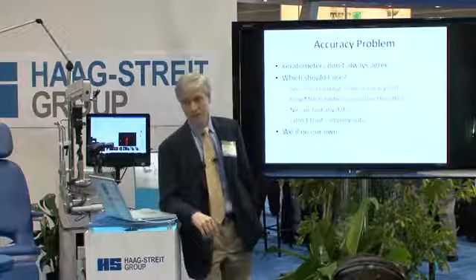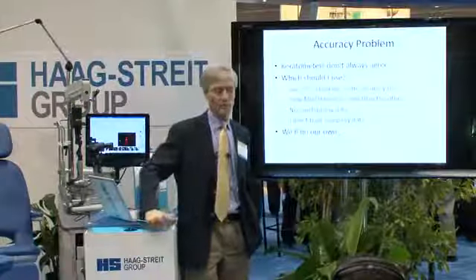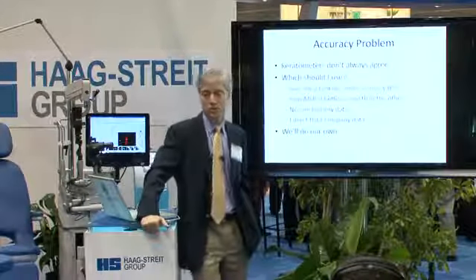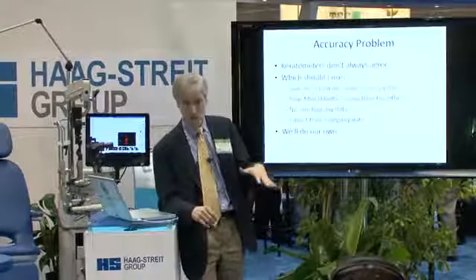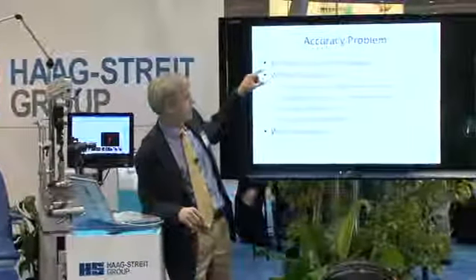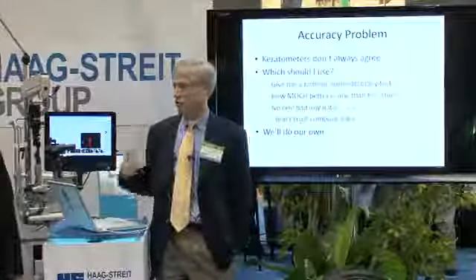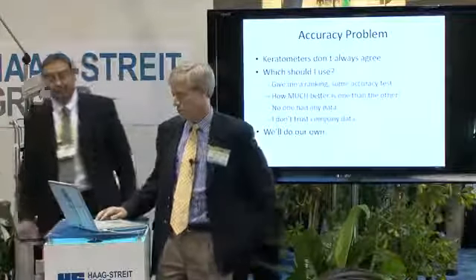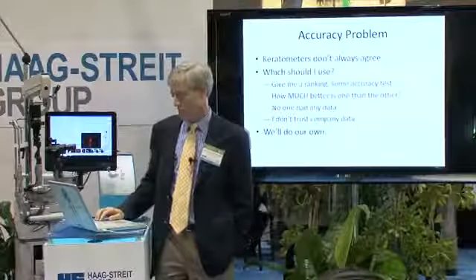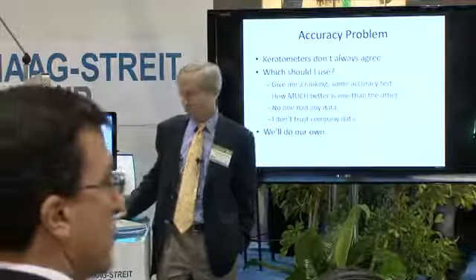That's consistency. But I'd really like to know about accuracy, because a machine can be consistently wrong. In fact, our Bausch and Lomb Manual keratometer was consistently wrong — nice and consistent, but not very accurate. So how do we determine what's accurate? What I'd like is a ranking so that when two machines give different readings, I know which one I can trust. I don't trust company data, so we did it ourselves.